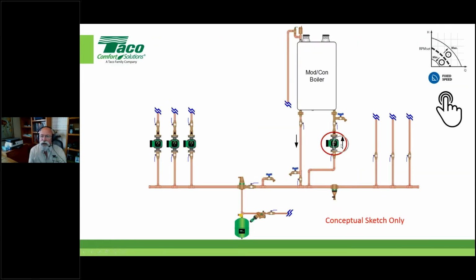So notice, no more control wire. It's very important now to get this circulator size correctly, and we will talk about that. We'll give you some hints and some things that in some cases change the way you've been thinking about things. I know others have noted that and said, yeah, I've been oversizing that pump. Well, that's what these seminars are supposed to do, get you to quit just doing the boilerplate stuff. Start thinking about what you're doing and why you're doing it, and be able to back up why you're doing what you're doing. And that's what Taco is trying to do here, make sure you have a better understanding of why you do what you do and why you size the way you do.